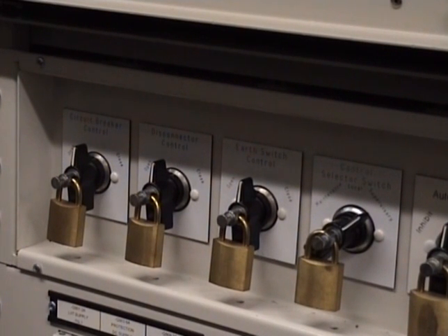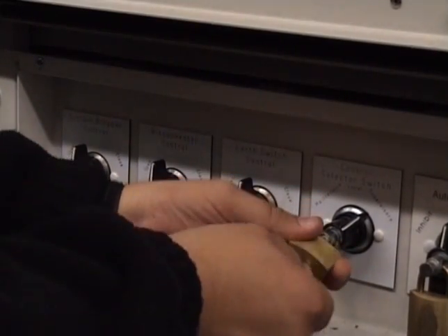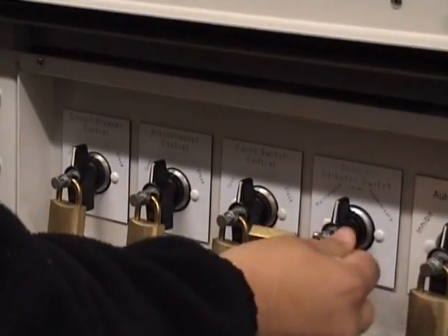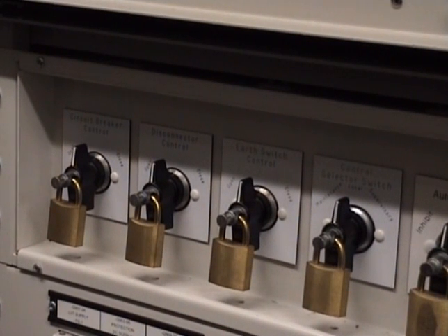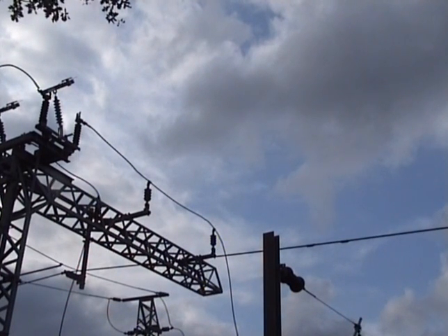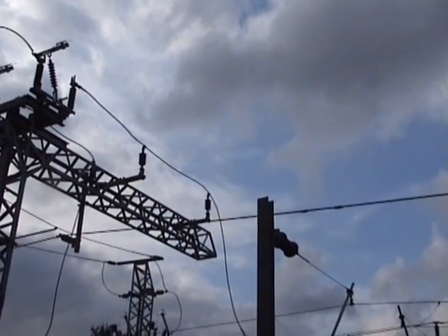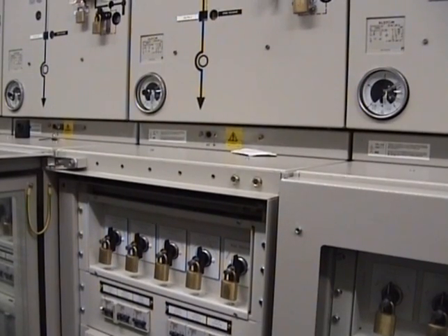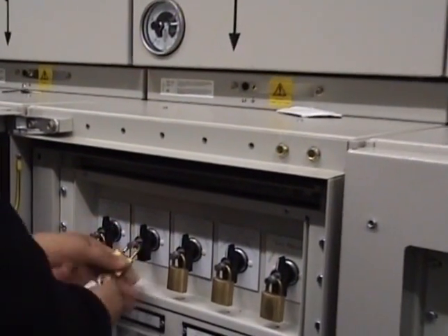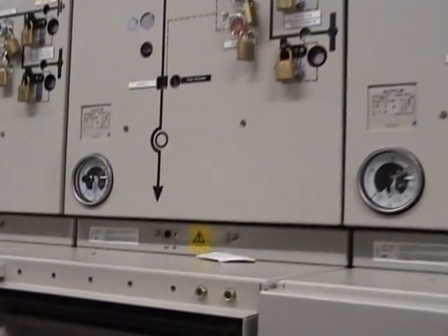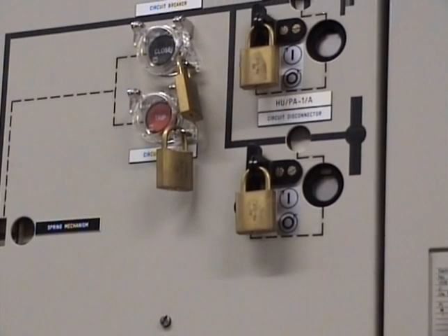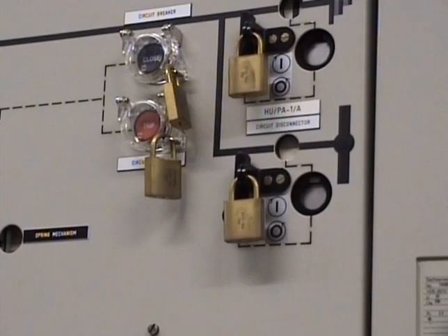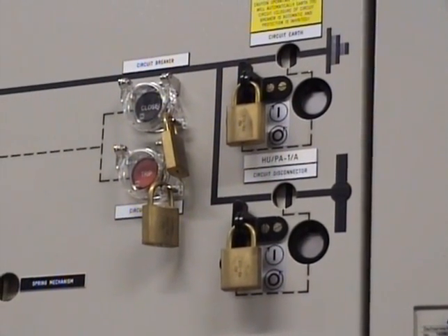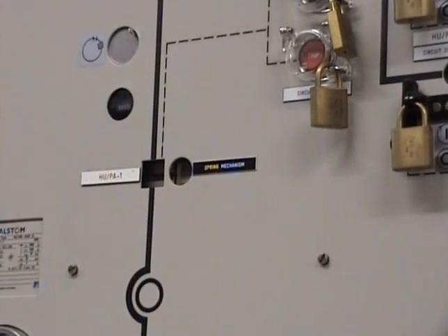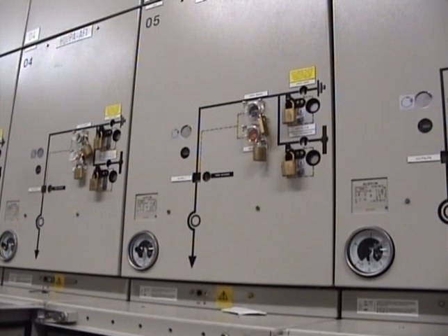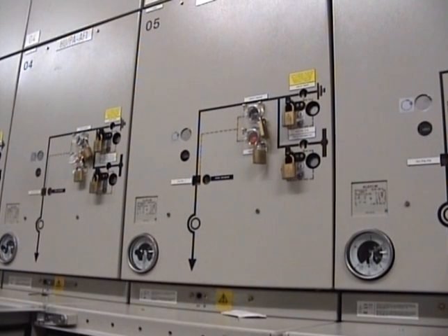We are now going to operate the control selector switch from supervisory to local. This has ensured that the breaker cannot be opened or closed remotely. Next, we open the overhead line switch, which disconnects the cable and switchgear from the contact wire. Next, we operate the circuit disconnector. We are now in the open position with the circuit disconnector and the open position with the circuit breaker. Having isolated the cable, our next action is to test it and then connect it through to earth.